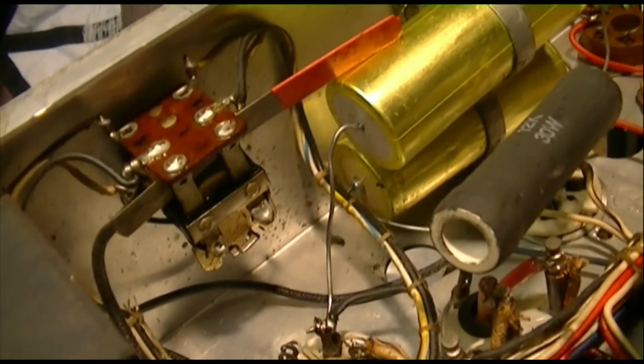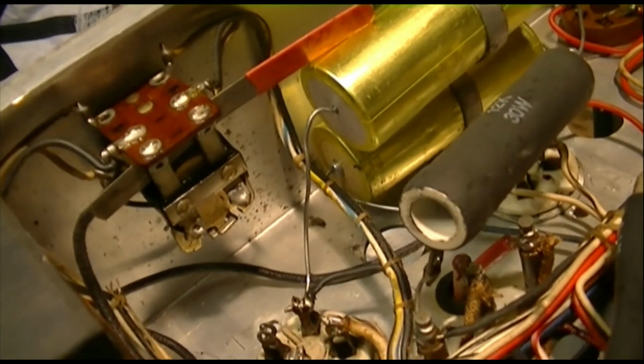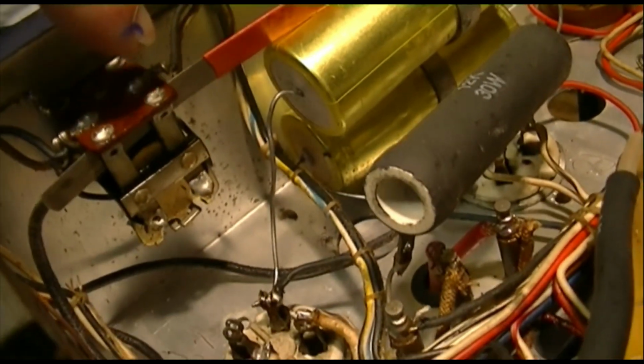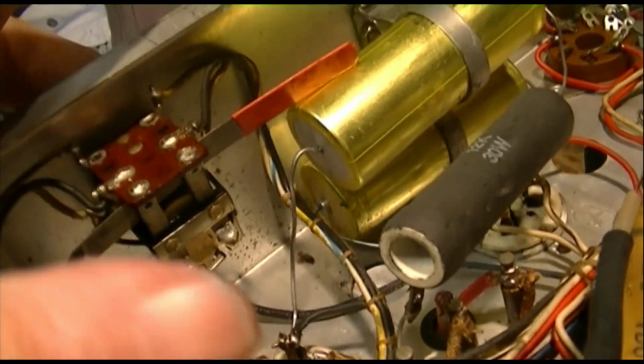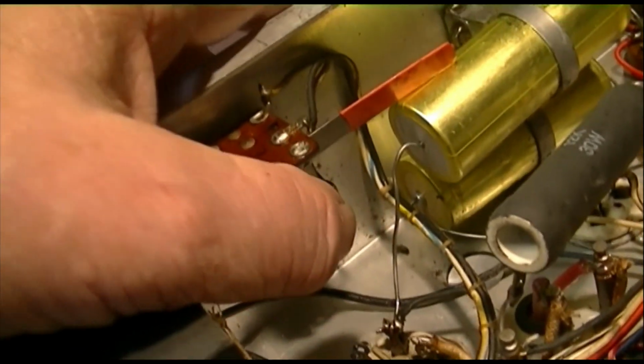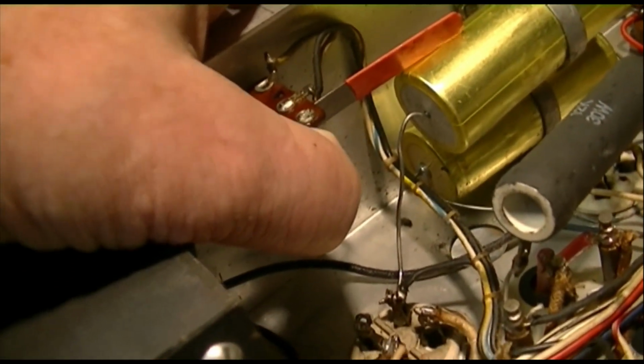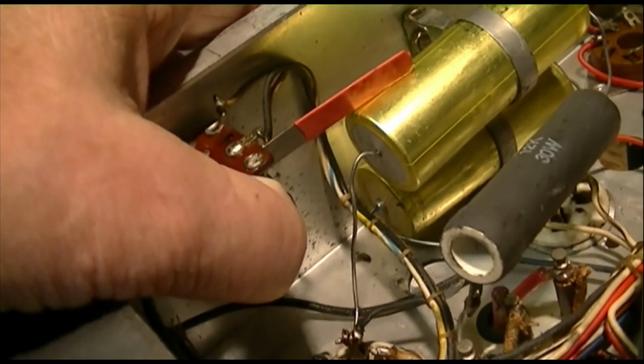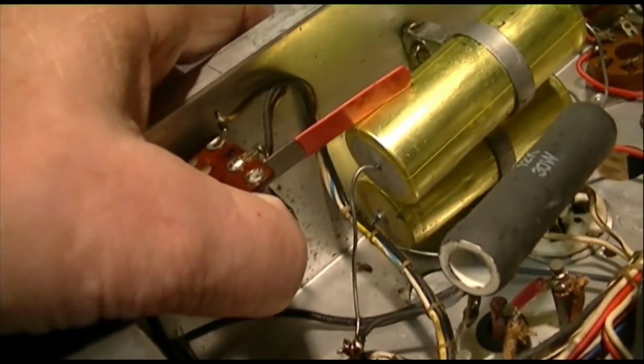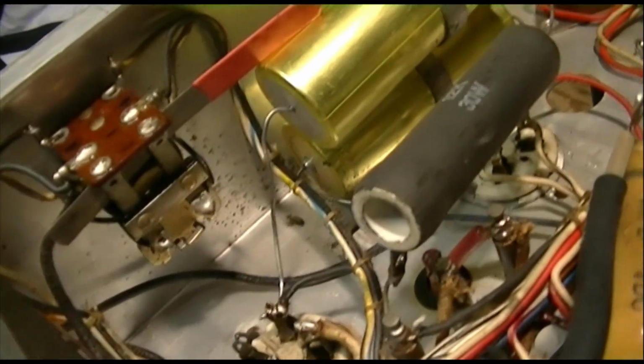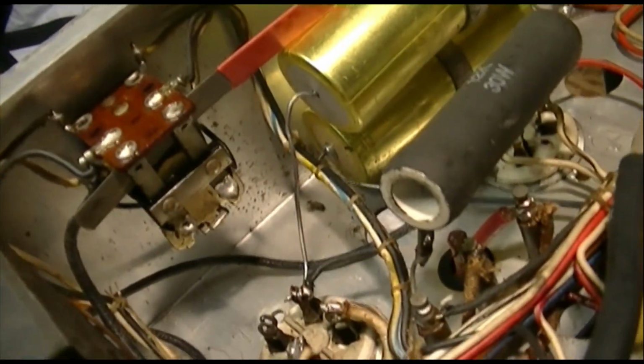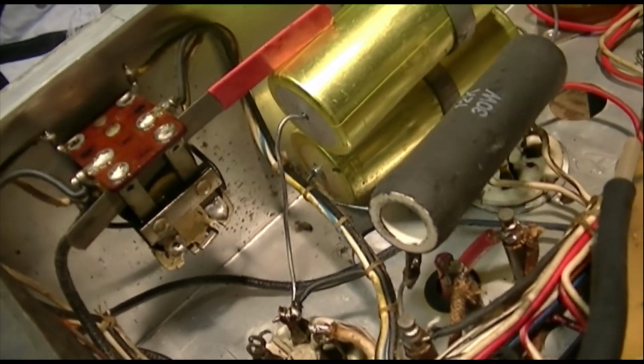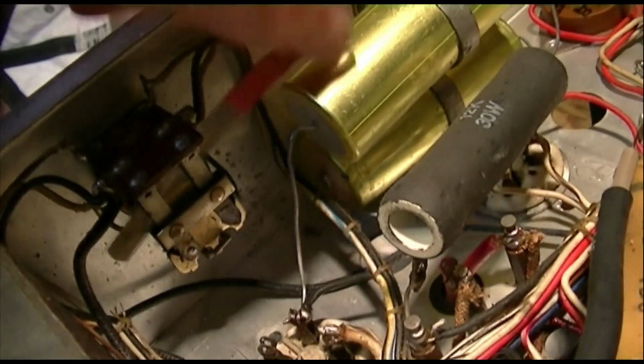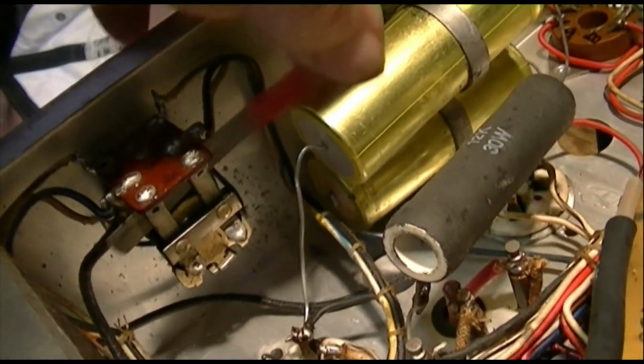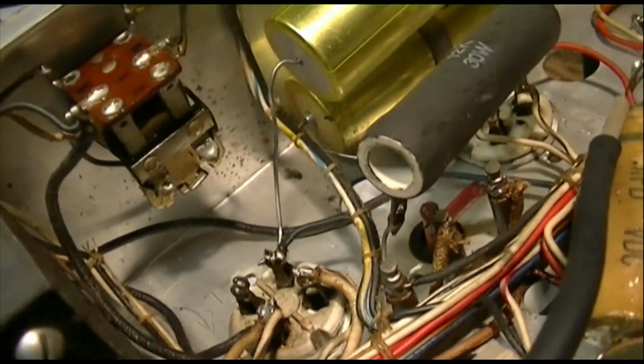No magic to cleaning the contacts. Get your burnishing tool between the contacts, spray it with a little DeoxIT, put a little pressure on the contacts by closing the relay with your thumb, and pull the burnishing tool back and forth. Half a dozen times and it's probably going to be fine, unless they're pitted and screwed up. Just a little bit with a little pressure on there, and you're good to go.